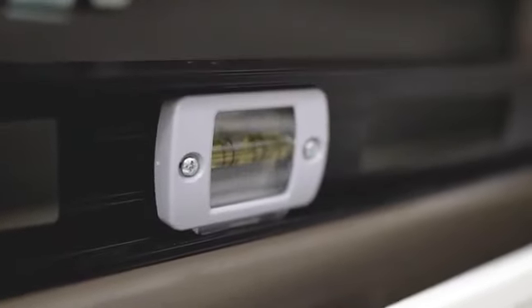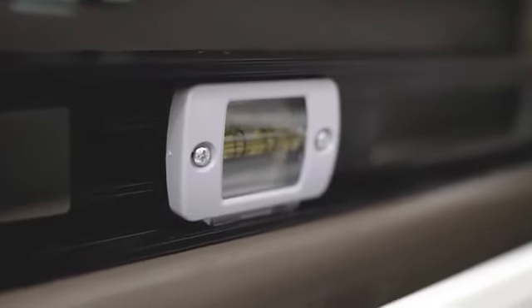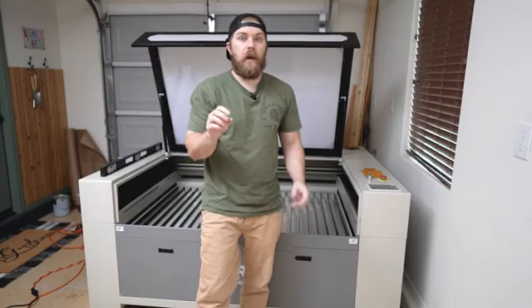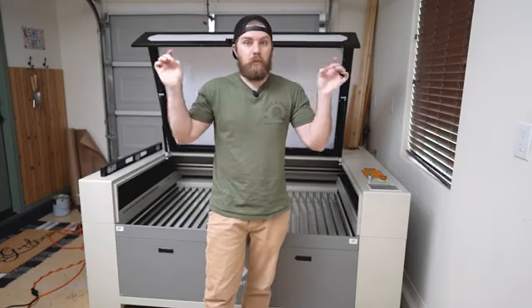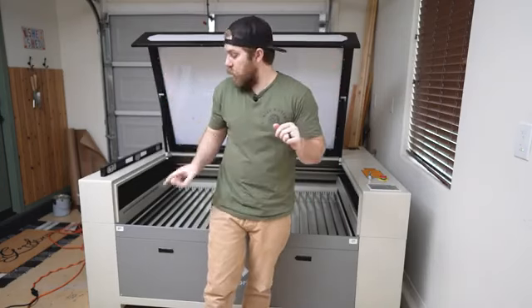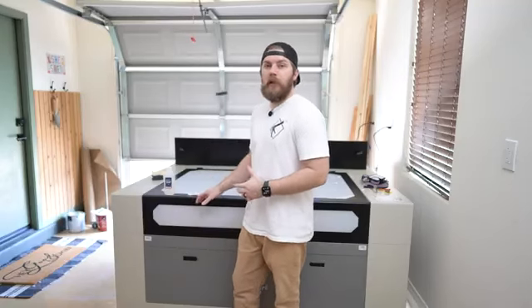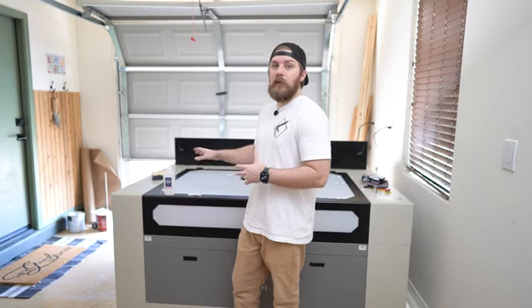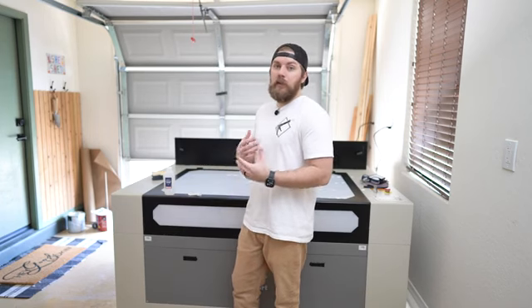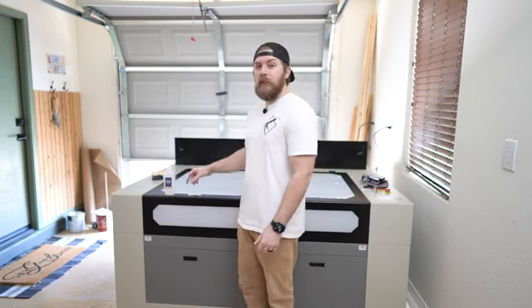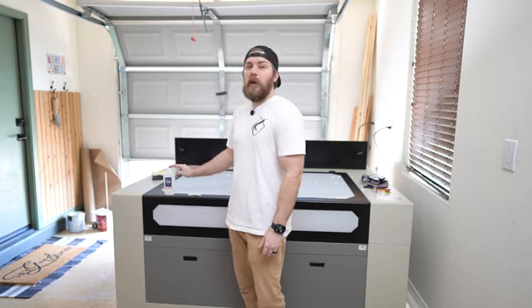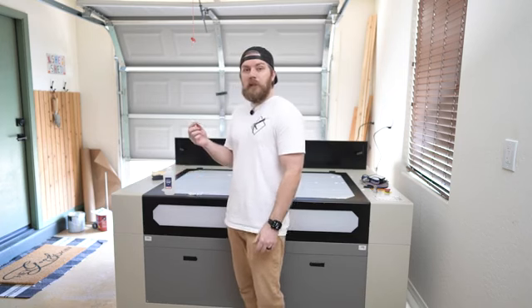And again, they don't have to be perfectly level. The bubble doesn't have to be in between those two lines, but you want the bubbles to mirror each other. If they don't, you're gonna use your leveling feet and crank it out until they do. The next step I'm gonna complete as part of the setup is to align the mirrors. Before we do that, at least in my case, I'm gonna clean them with 99% isopropyl alcohol and some Q-tips.